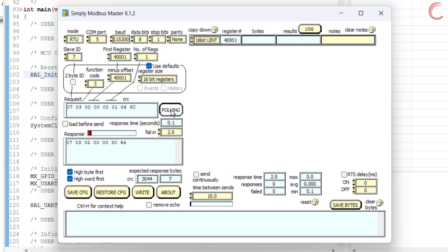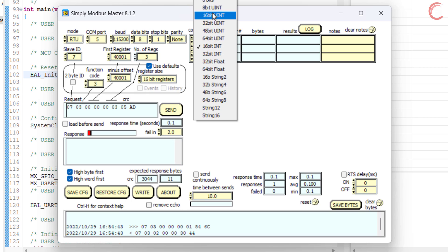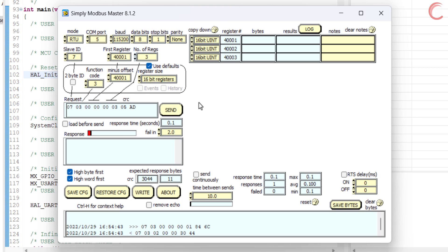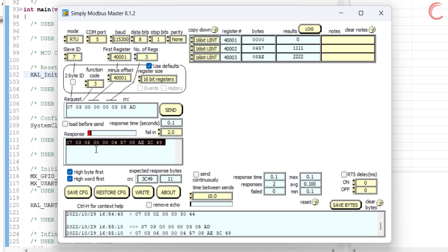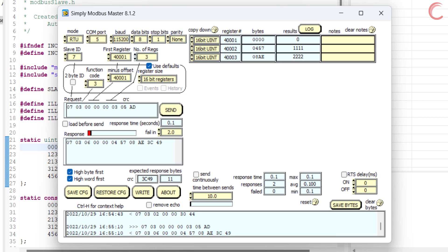Press the button to send the query to the slave. The master has received the response. Here you can see the data received for the register at 40001 is 0. Let's read three registers now, starting from the same address. Here you can see the response received by the master. It contains 11 bytes, and this is the same as what the master was expecting. Here you can see the data received for the respective registers. If you check the registers database, it is the same data that we stored here.